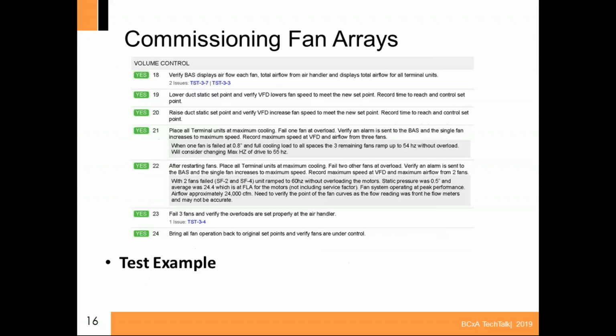So here are some of my scripts that I go through that I'll let you guys have. Here's one that I did on a small fan wall. If you look at number 21, line 21, I placed them all in cooling, and I tripped one of the fans. And I maintained the 0.8 inches of what I needed. And the fans ran at 54 hertz without overloading, so I changed it from 54 to 55, okay? And then from there I failed another fan. So when 2 fans were failed, this would be script number 22. I went ahead and ramped up the drive to 60 hertz, because it wasn't overloading.